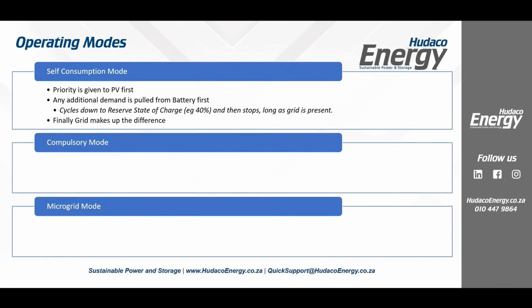Normally, if we set it from 0 to 100%, and I'm going to use a 16 kilowatt hour system, for example, if I set my battery range from 0 to 100%, it means all 16 kilowatt hours are fully usable. There's no impact on warranty. They are designed to do that. In fact, the battery capacity is slightly higher, but because the BMS and the batteries talk directly to each other, we don't need to do any other settings on that. The entire commissioning process of the battery to the inverter is a total of 10 seconds. It does it automatically, by itself. You don't have to worry about it.